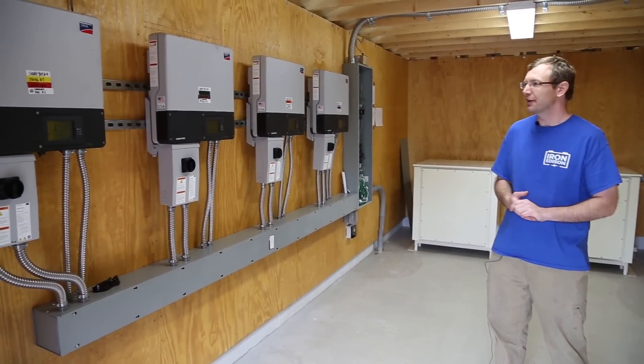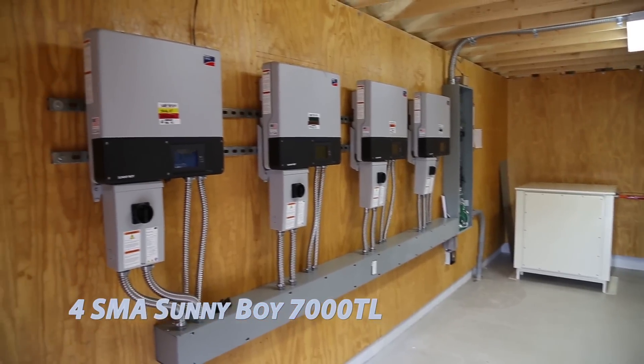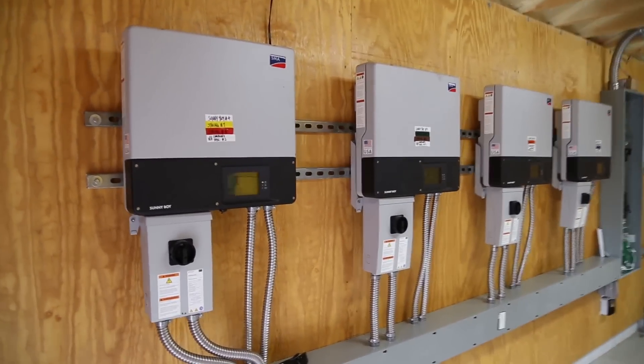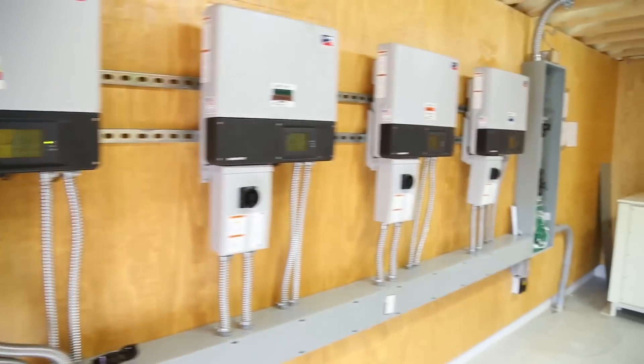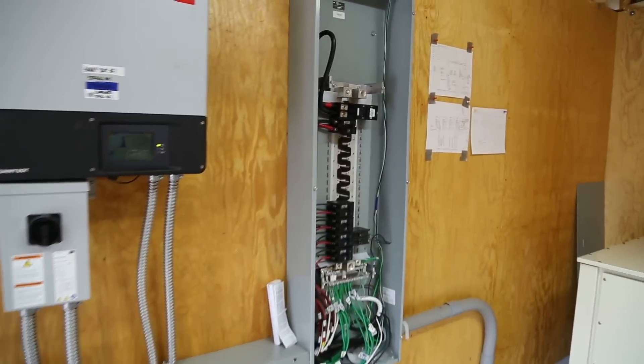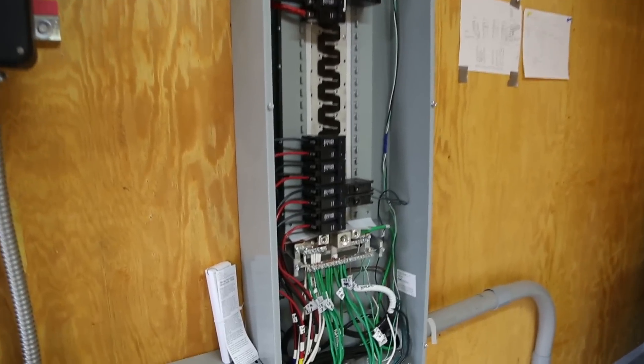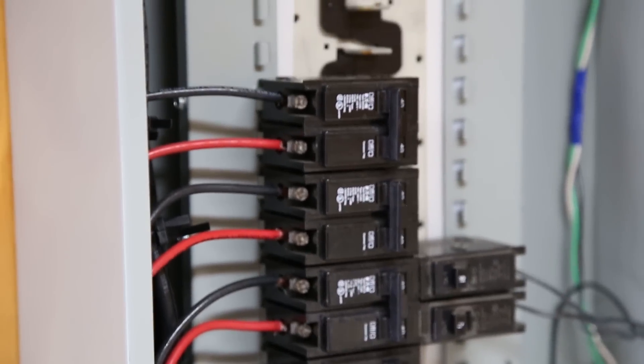Let's take a closer look at all the equipment here in the inverter room. On this wall we have four SMA Sunny Boy inverters, each rated at 7,000 watts. They're taking the solar power in DC and creating 240 volts AC out. We have an AC combiner box where the output of the SMA inverters comes together and feeds a dedicated circuit breaker box. The output of this circuit breaker box is going to feed the inputs of the SMA Sunny Island inverters located on this wall.